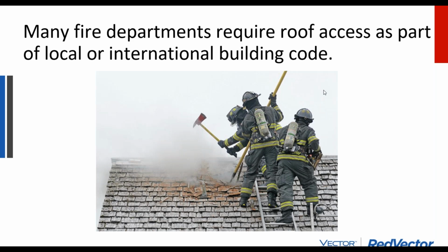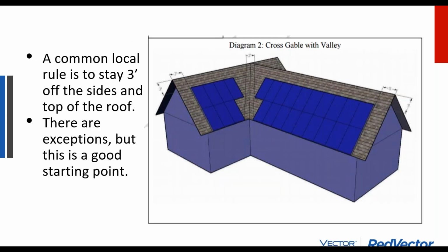Now, I think firemen should actually like solar quite a bit on a rooftop because the metal framing from the solar array itself adds some strength to the rooftop. So a roof with a solar array on a racking system on top should stay up longer during a fire, not collapse earlier than one without. A little bit of a different case with certain types of racks and certain maybe flat roof commercial systems. The takeaway is we have to consider the firemen in our designs.